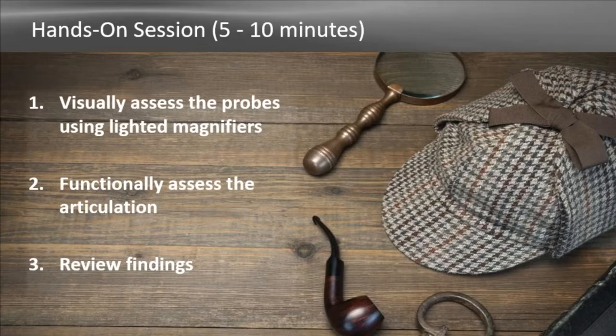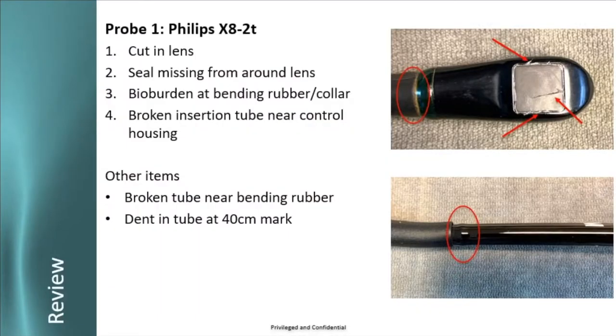Okay, let's review what we had. Probe number one, here it is, the Philips X8. Tiana saw that we had a cut in the lens and a seal missing. What we didn't see is bio burden at the bending rubber or collar. You can see this brown residue, internally we call it crud. These probes have been decontaminated, but when materials are missing, it will aggregate bio burden and debris. We also have a broken insertion tube near the control housing, down by the control housing, this insertion tube is broken.